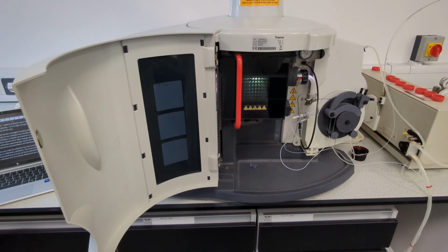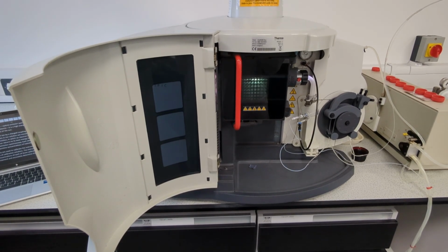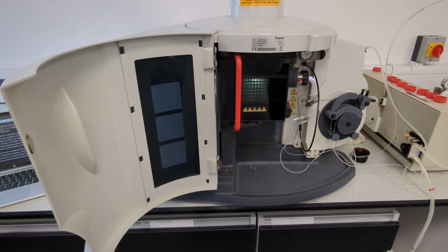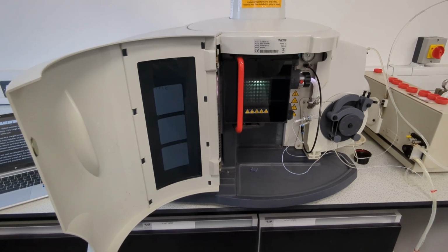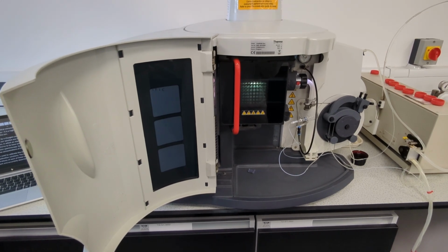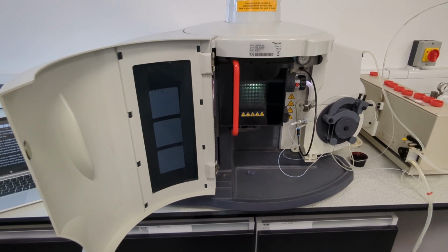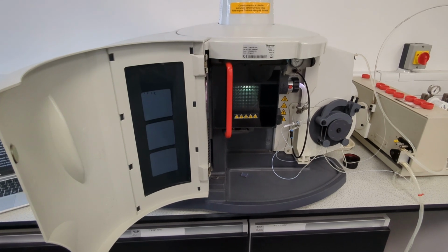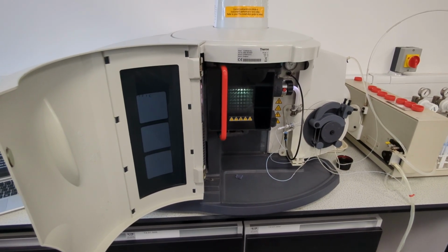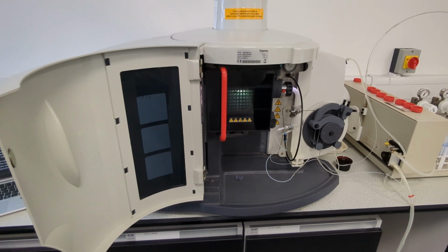When metals in our solution are introduced to the high-energy plasma, they undergo a process called excitation, in which an electron is elevated to a higher energy level than its base state. When the electron returns to its base energy level, it emits light. The detection of this emitted light is optical emission spectroscopy. Each element emits signature wavelengths of light, allowing us to determine concentrations of individual elements.